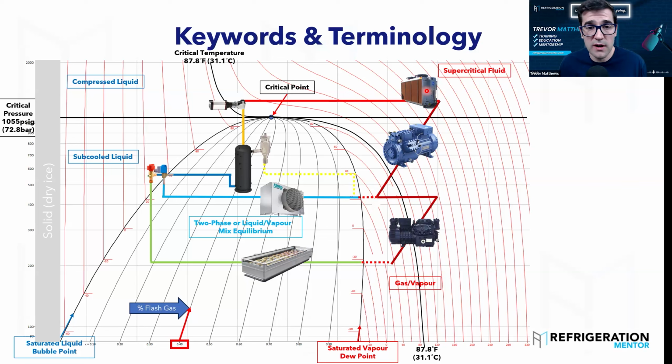I see tons of different models out there. I'm seeing some now where they're keeping the systems in subcritical at all times, which is amazing. If you can keep this system in subcritical at all times, it's going to be way more efficient than if you're running in transcritical all the time. So that's the goal, to keep it below transcritical, so you have liquid coming down the drop leg, not fluid down the drop leg. Okay, and then right here, we push out a little further.